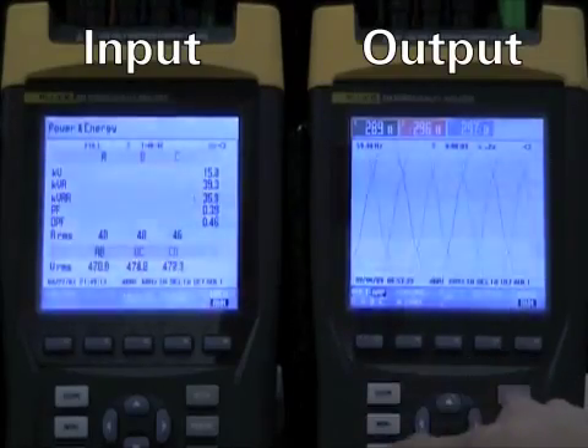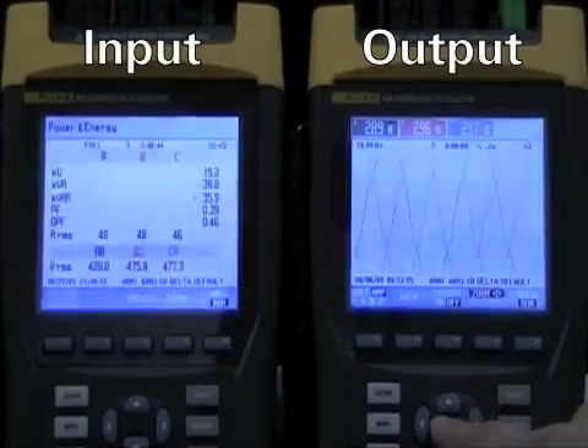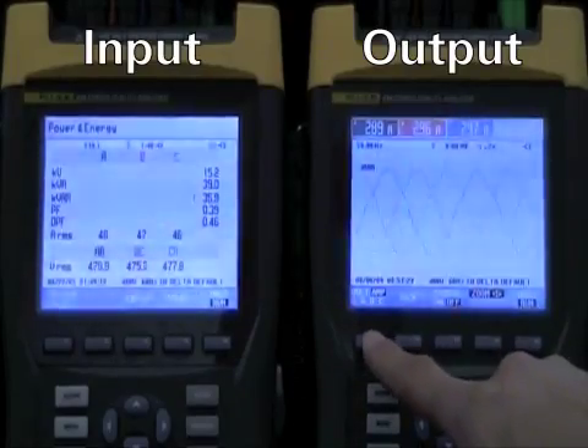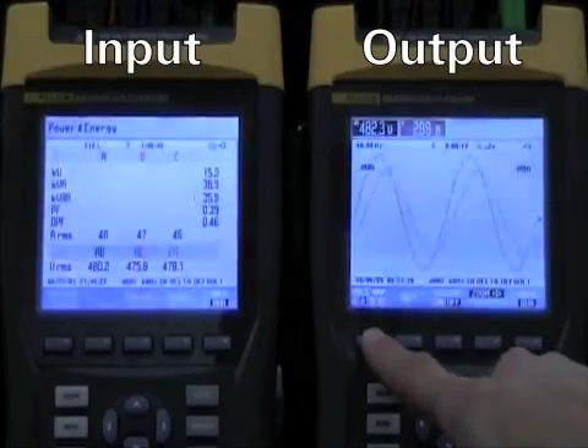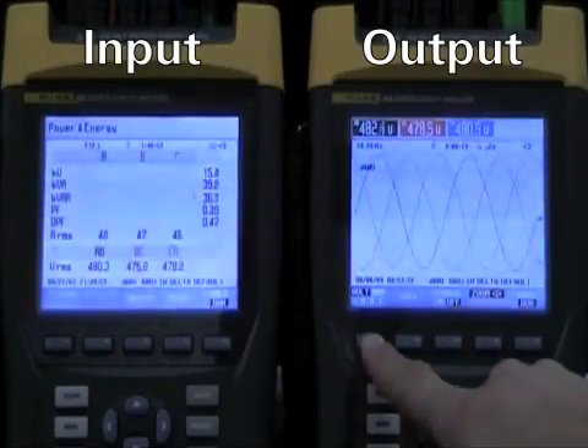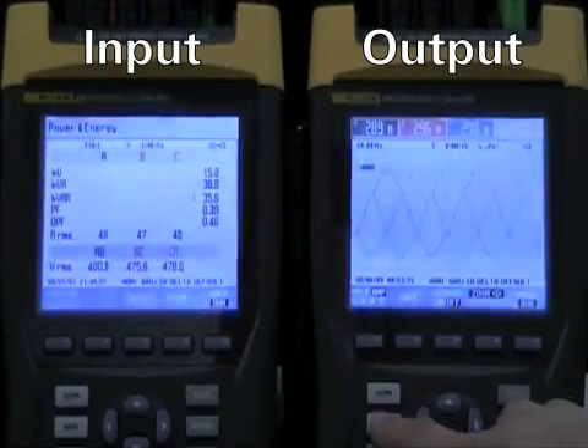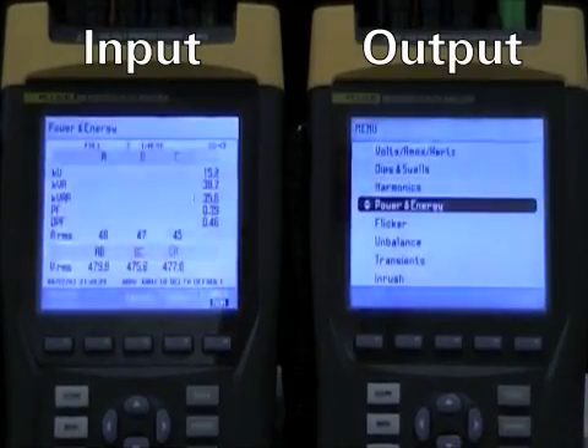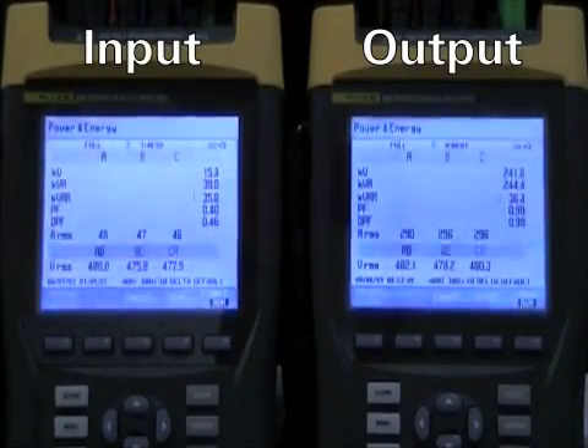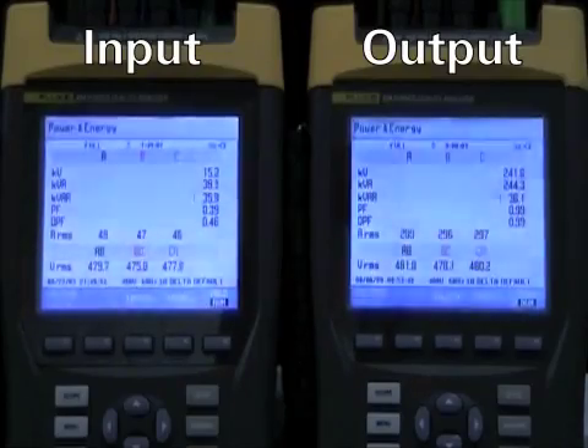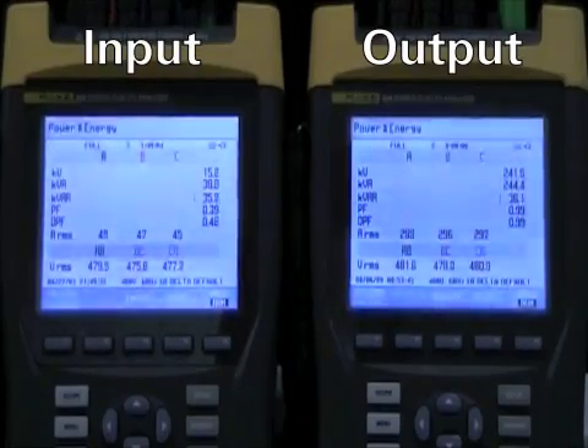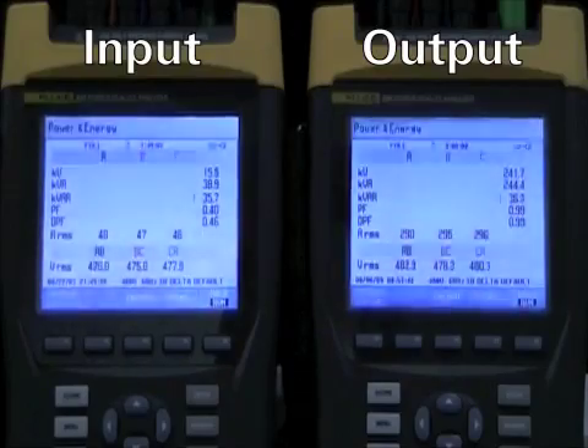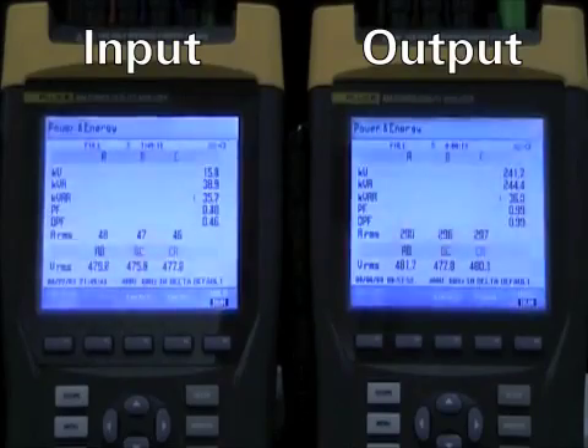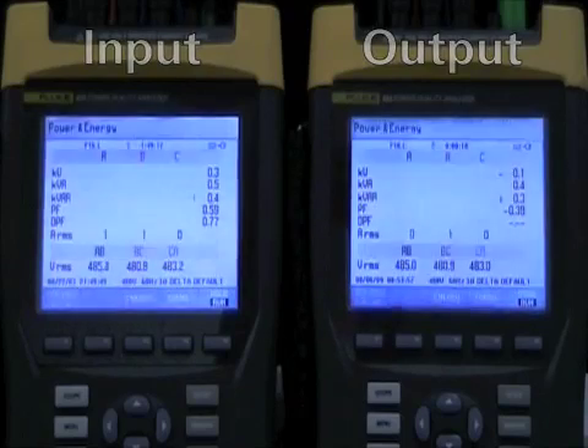Now on the right-hand side, we're displaying the output voltage and output current during the test. So you can see the UPM is actually under real load. Now we revert back to the kilowatt display. And the easy capacity test is concluded.